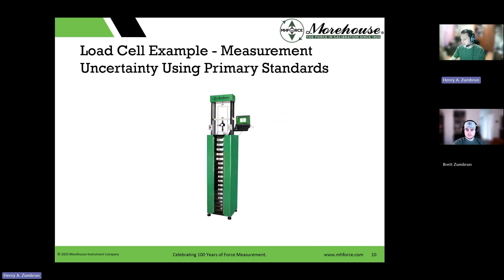Now, these dead weight machines are primary standards, which is defined by ASTM as weights that have been calibrated with considerations for the material density, adjusted for local gravity, air buoyancy, and that are machined with a surface finish according to ASME. That's basically a generalized finish any turning center usually achieves. So if we look at this and look at our 5 Rs, they're there.